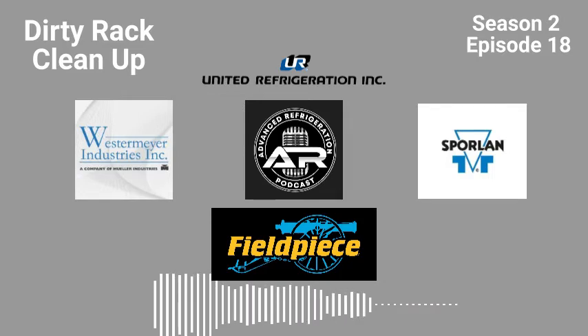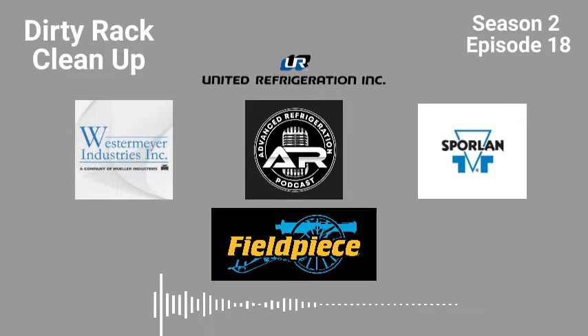Any kind of hot gas that's bypassing wherever it wants to go during defrost might not be getting filtered. So you're wondering why it isn't getting clean. I've changed the filters. I changed the coalescing filter on the separator 60 times. Why isn't all the crap coming out?